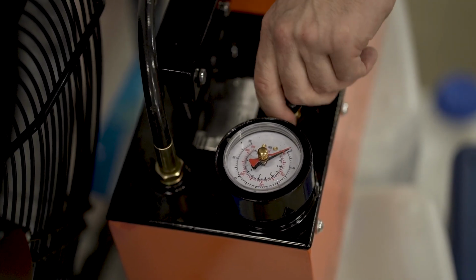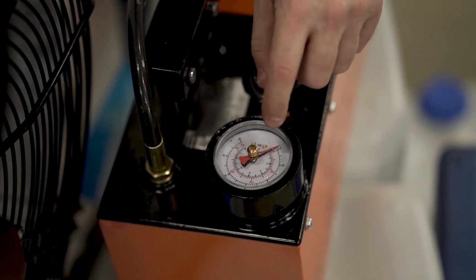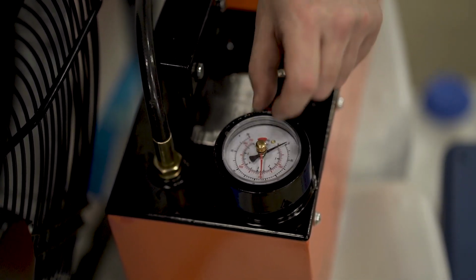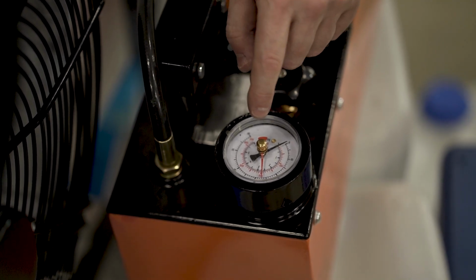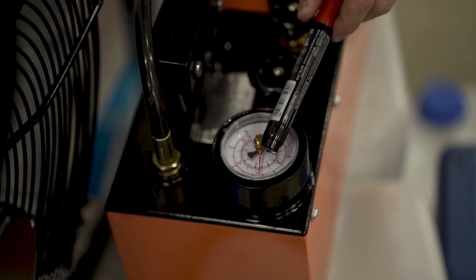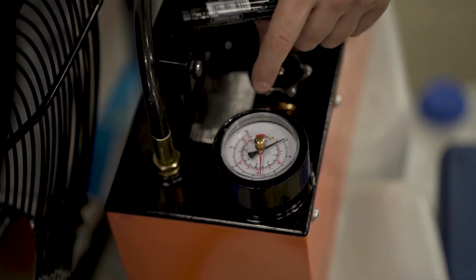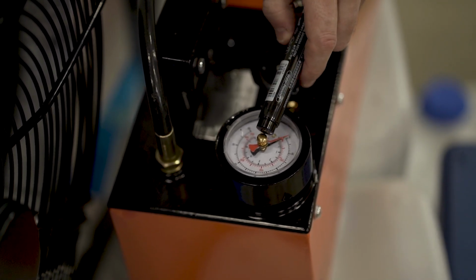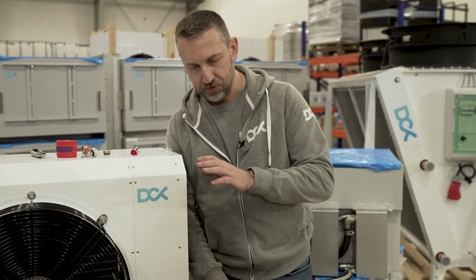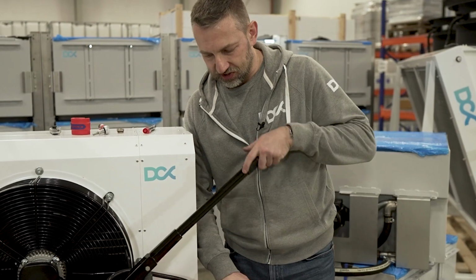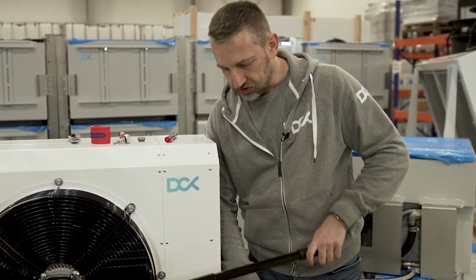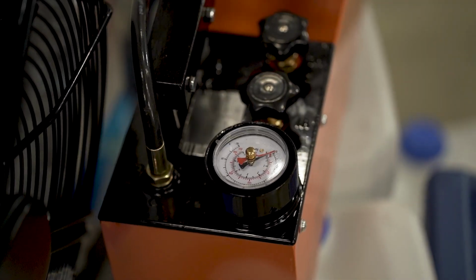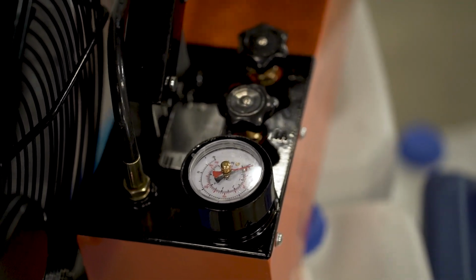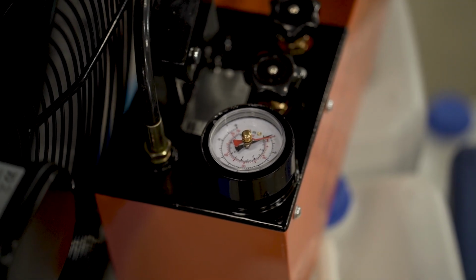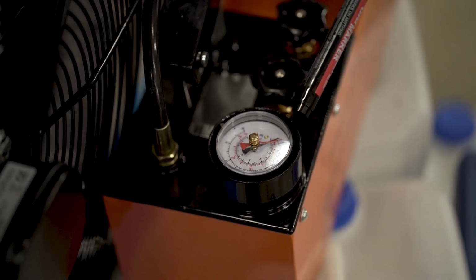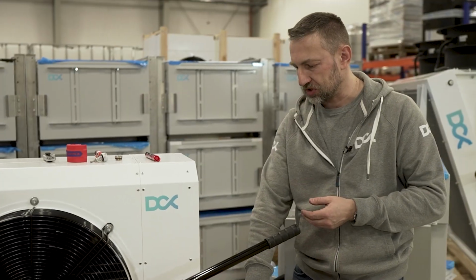I close valve 2. I open valve 1 counterclockwise. I reset the manometer, and you can see that you have the temporary measurement of the maximum pressure in the system, which is indicated by that red arrow here. To reset that, you just turn the yellow screw in the middle, right? Simple as that. Now what you need to do is just pressurize the system by wiggling that handle. Right now I'm pushing the water into the system. As you can see, the temporary pressure indicator is gradually adding more pressure into the loop.